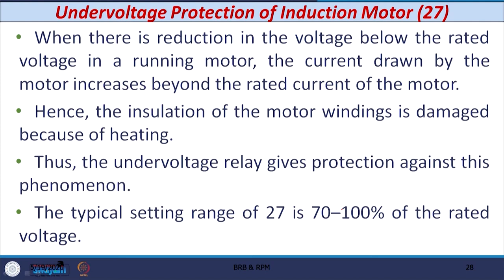The next phenomenon is undervoltage protection of the induction motor, and the relay number is 27. When there is a reduction in voltage below the rated voltage during running condition, the current drawn by the motor increases beyond the rated or full load current of the motor. Hence, the insulation of the motor windings is damaged because of excessive heating. The undervoltage relay gives protection against this type of phenomenon, and the typical setting range is 70% to 100% of the rated voltage.